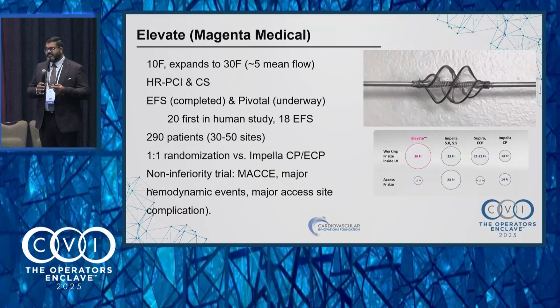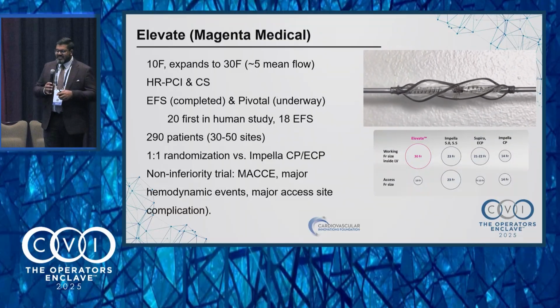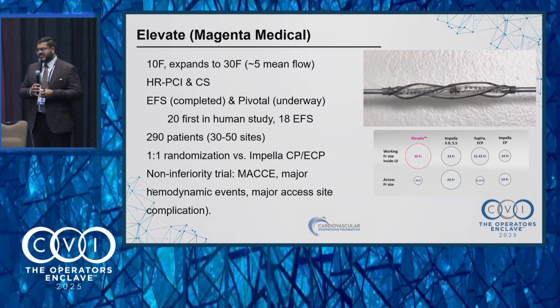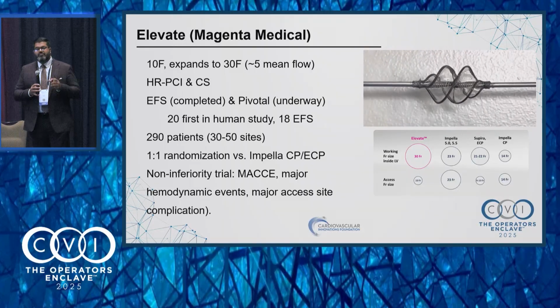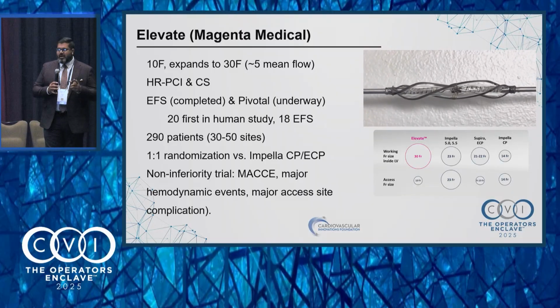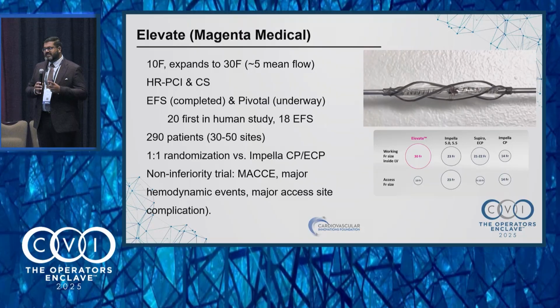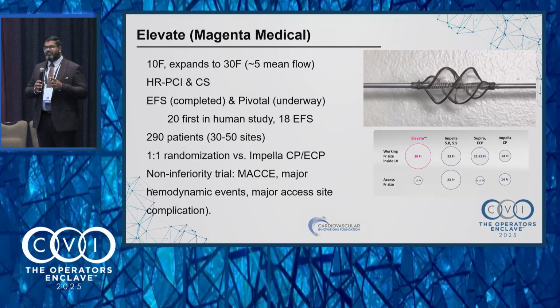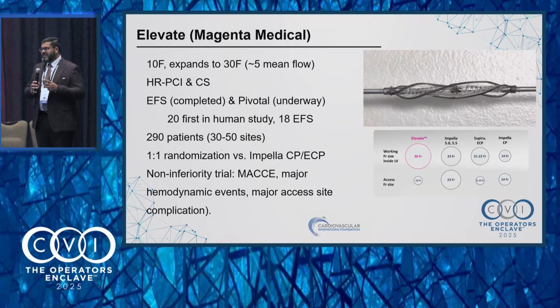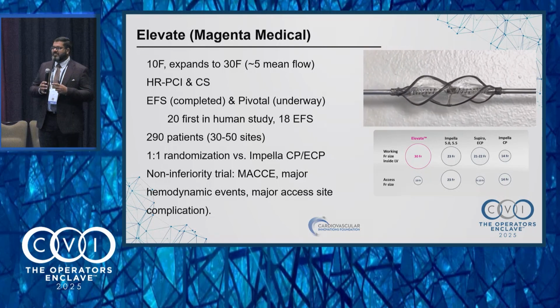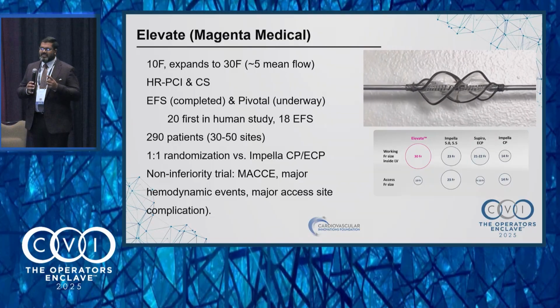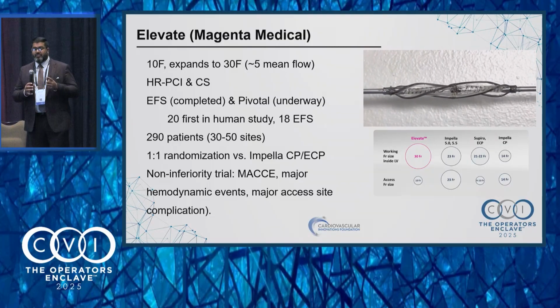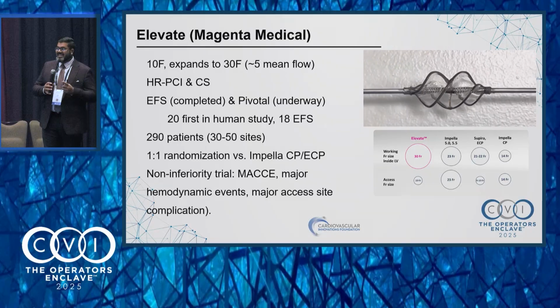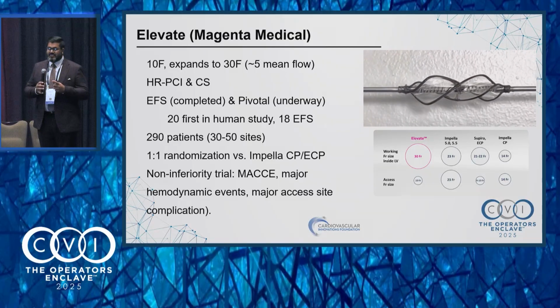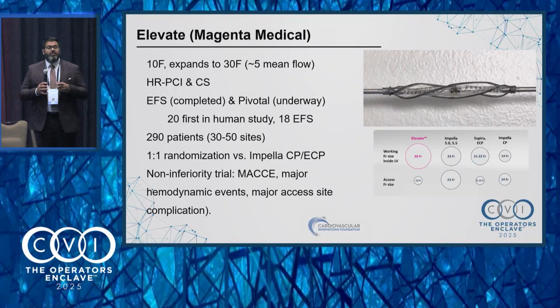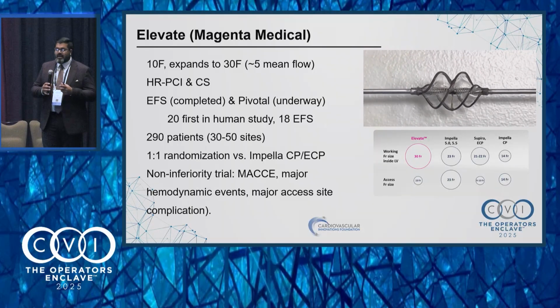The next device here is the Magenta device, or by Magenta Medical, the Elevate device. So this is a 10 French over-the-wire device, very accustomed to placing it very similarly to an Impella CP. It expands, however, to 30 French, and this is the largest device that we actually have available in terms of the impeller itself. And so it gives mean flows consistently of over 5 liters and peak flows as high as 8 liters. And so this is actually purpose-built for both high-risk PCI and for cardiogenic shock.